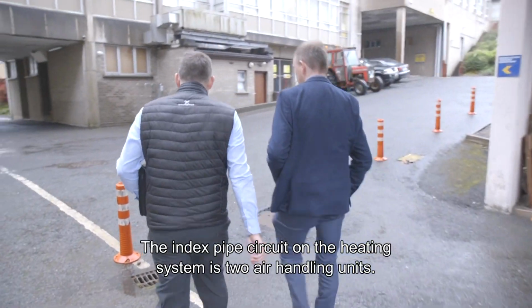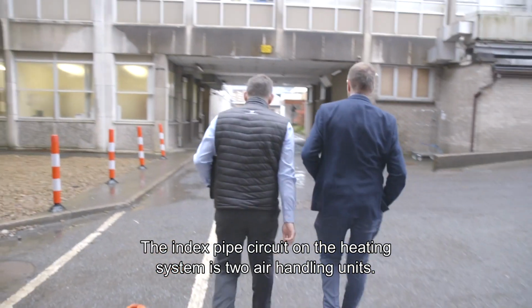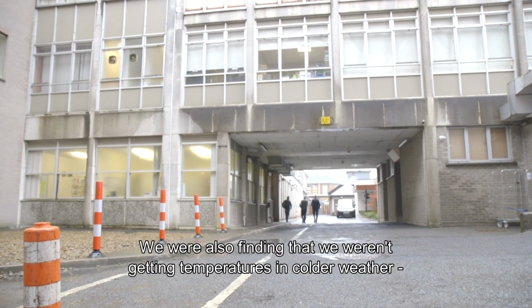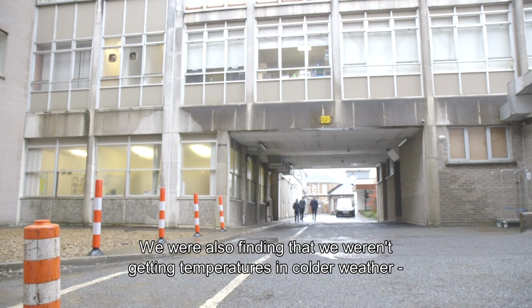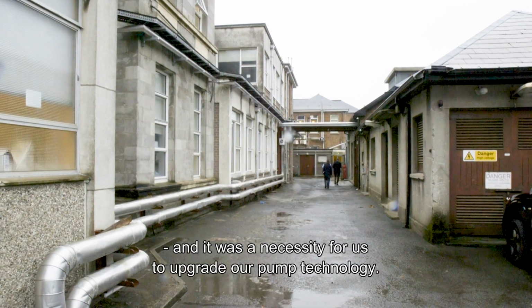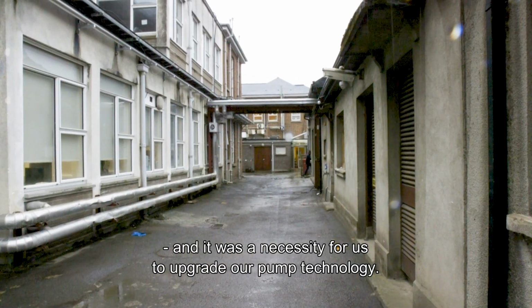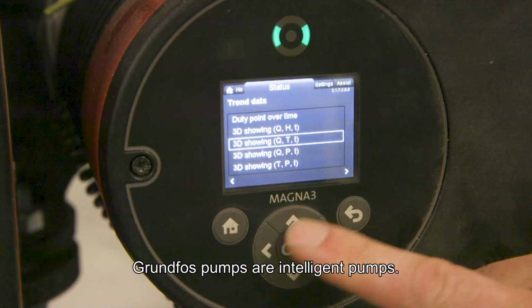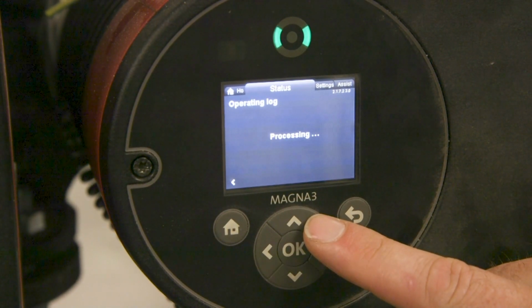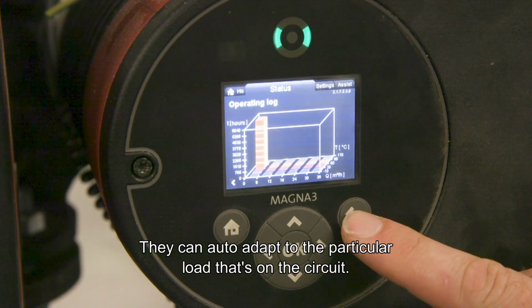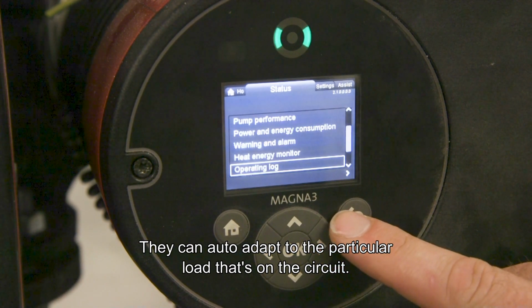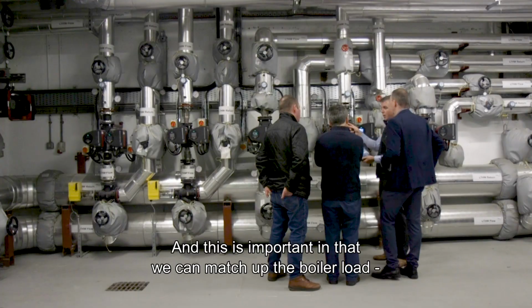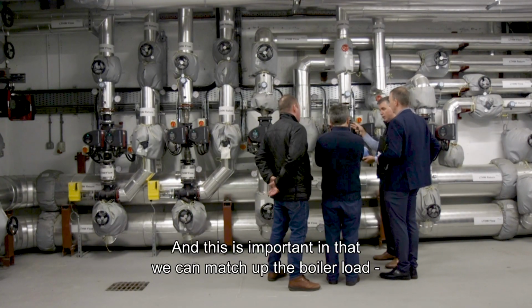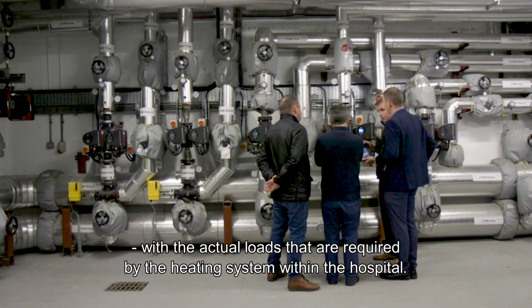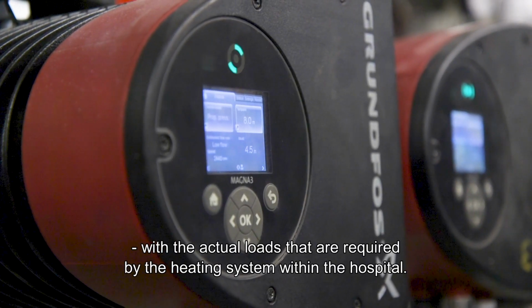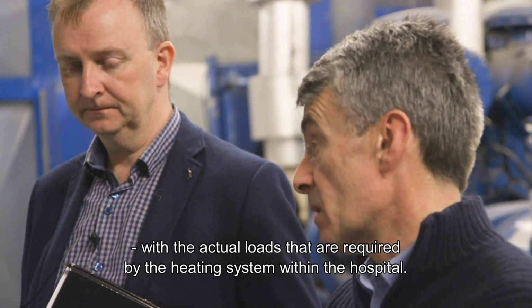The index pipe circuit on the heating system here is two air handling units, and we were also finding that we weren't getting temperatures in colder weather that we required, and it was a necessity for us to upgrade our pump technology. Grundfos pumps are intelligent pumps. They can auto-adapt to the particular load that's on the circuit, and this is important in that we can match up the boiler load with the actual loads that are required by the heating system within the hospital.